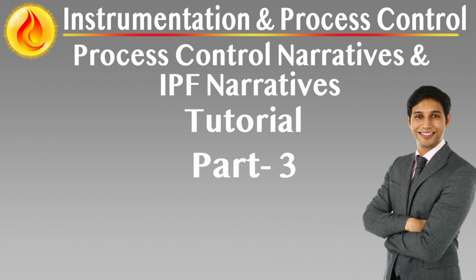Grouping for overrides and maintenance. If multiple IPFs share initiators or logic, the grouping for maintenance overrides must be clearly defined. This allows operators and technicians to isolate multiple related IPFs without compromising unrelated protections. Grouping is typically reflected in the cause and effect matrix through color coding or border boxes.